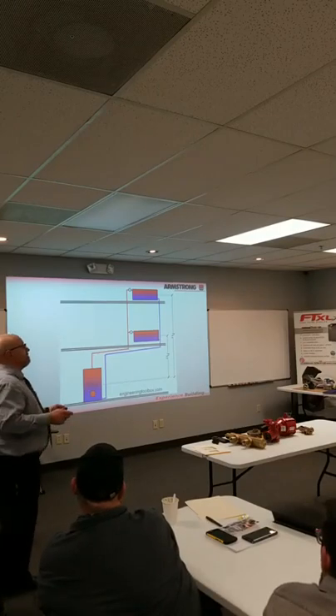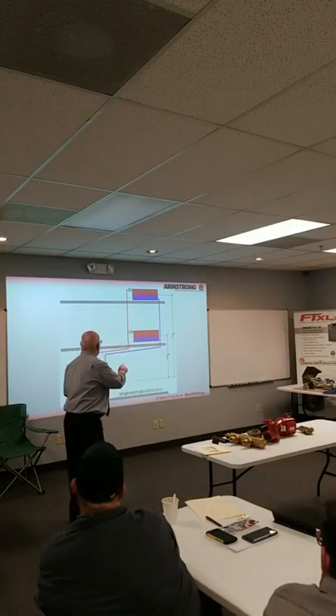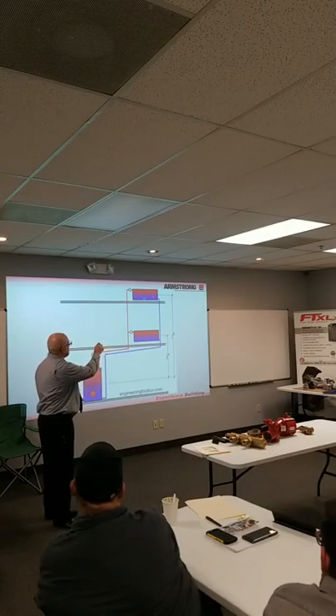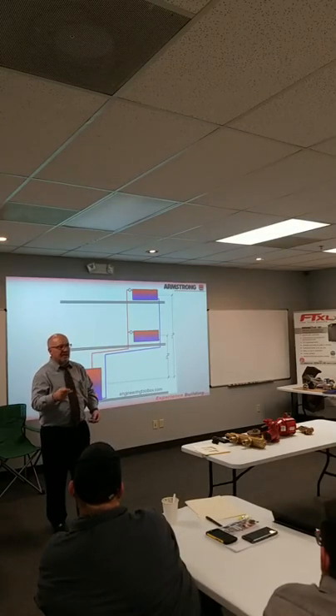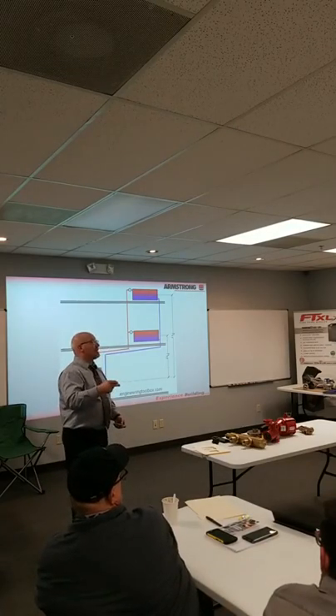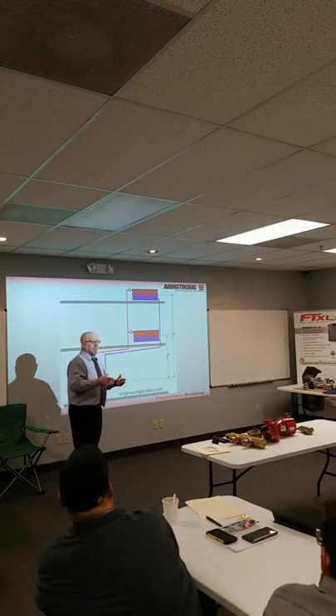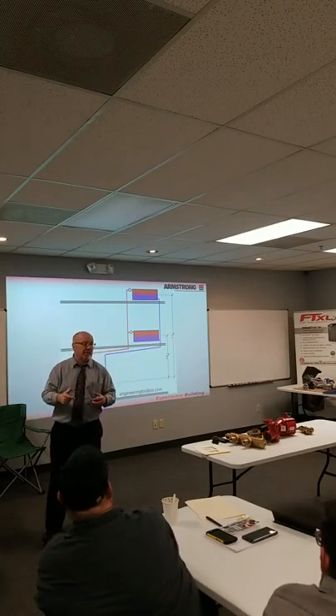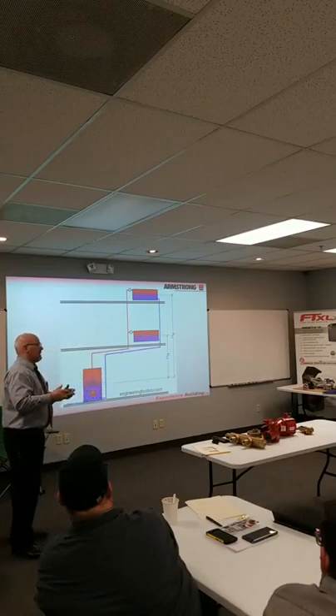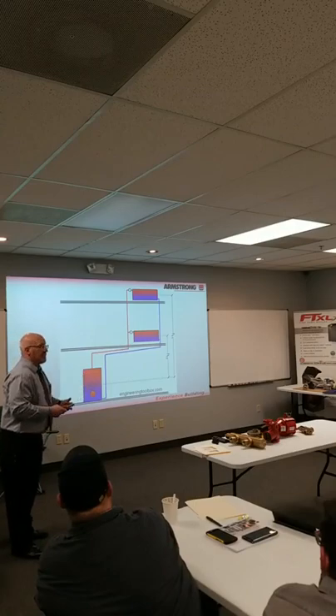No. Yeah. Natural circulation. You don't. As we heat water, it becomes less dense. And as the heavier, denser, colder water starts to circulate, there are a lot of gravity hot water systems in this area. There are. It's because they oversized the piping, and actually most of them were steam jobs converted to hot water because the piping was so large. They replaced some returns, made the piping large, no resistance to overcome.